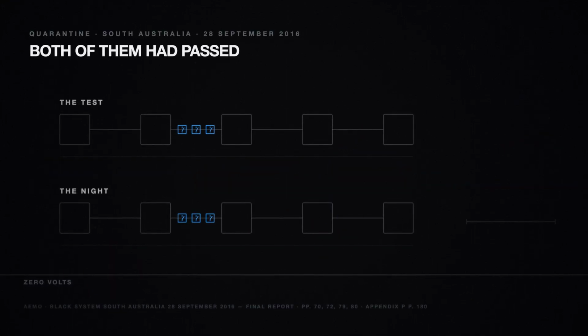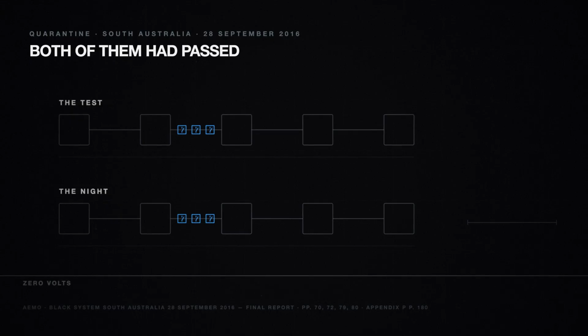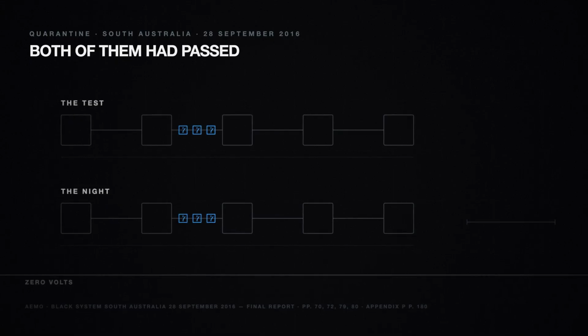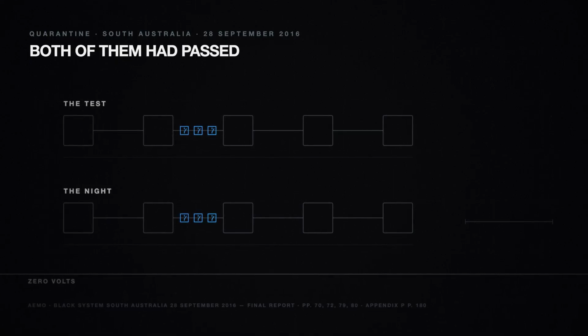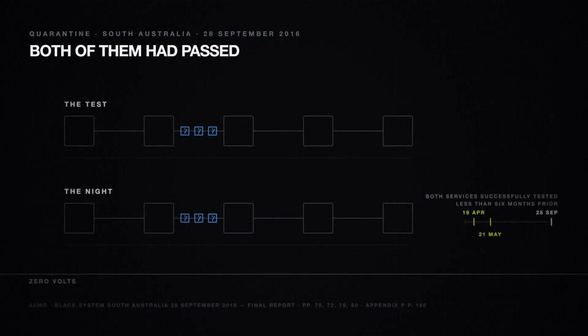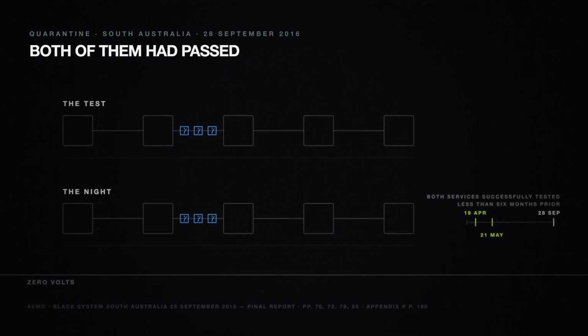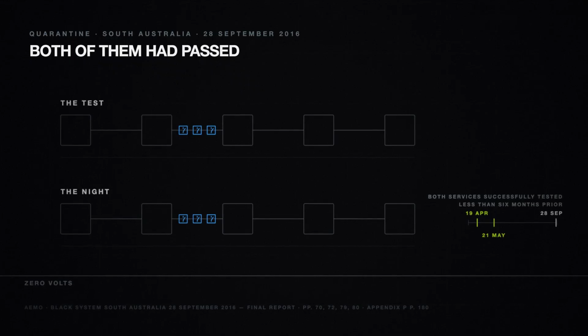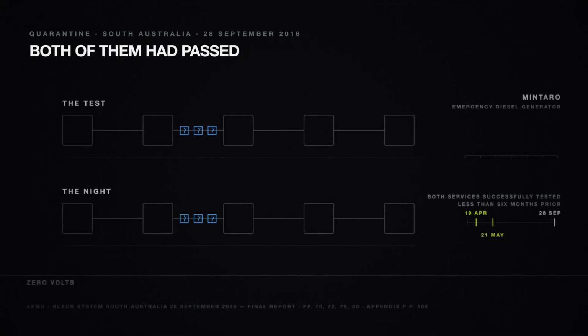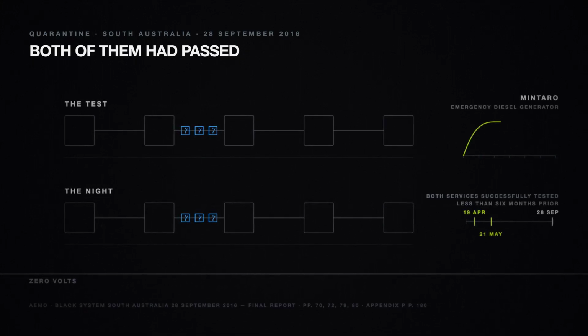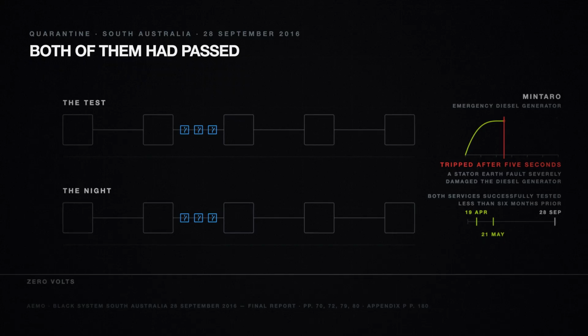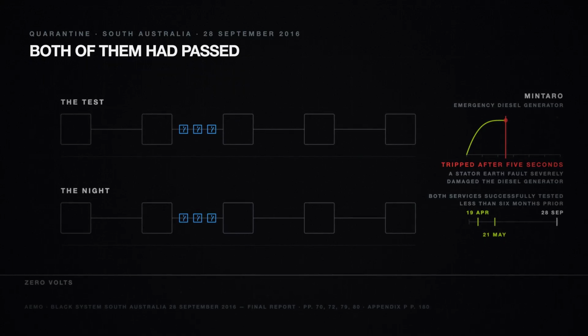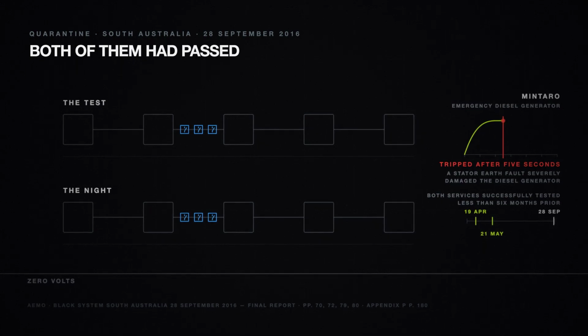South Australia, the 28th of September, 2016. The state's entire power system goes down. It had 2 contracted black start services, both successfully tested less than 6 months before, in April and May. Both failed on the night. At Mintaro, the emergency diesel generator tripped after only 5 seconds of operation, due to a stator earth fault, which severely damaged the diesel generator. Quarantine is the reason this film exists.